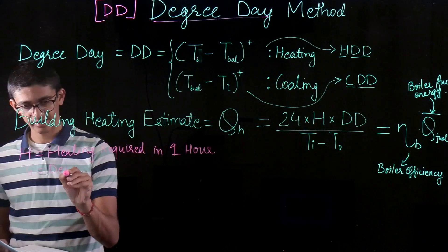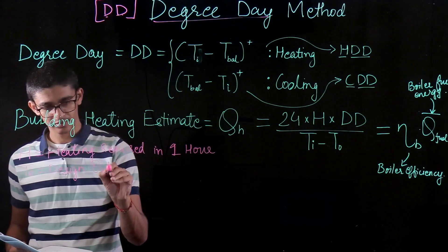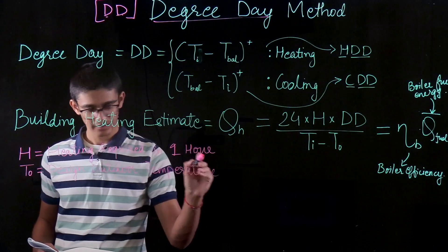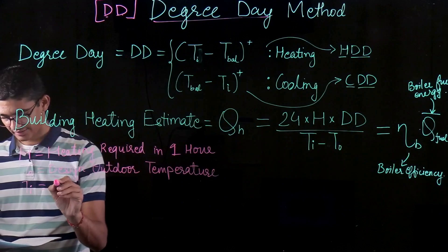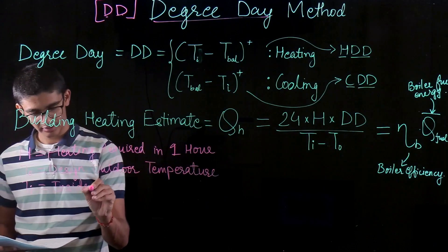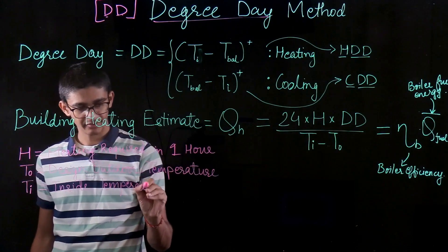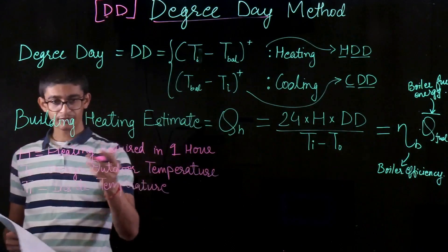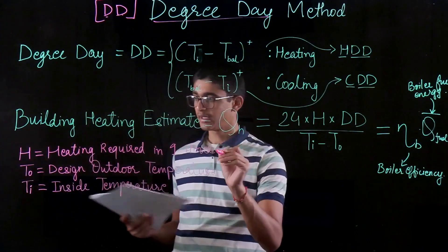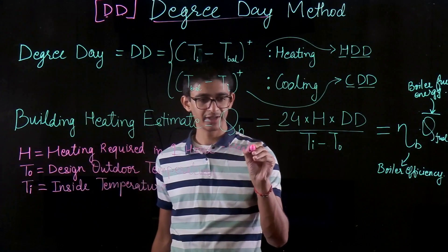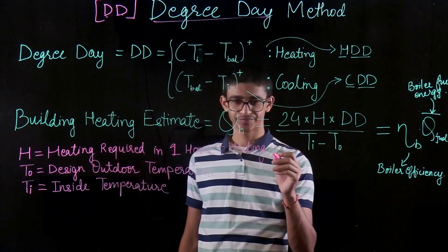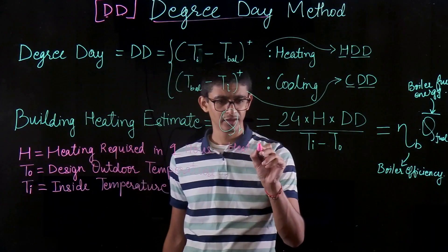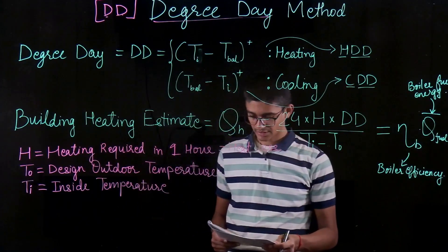T_out is the design outdoor temperature. T_in is the inside temperature, which is taken as 65°F — that is the balance temperature we want inside the room. H is the calculated heat loss of the building, meaning the required heating equals the heat loss. Whatever heat is lost must be compensated by heating.